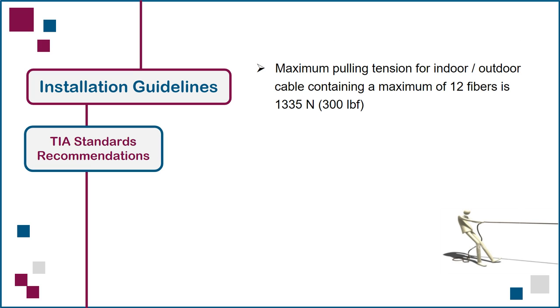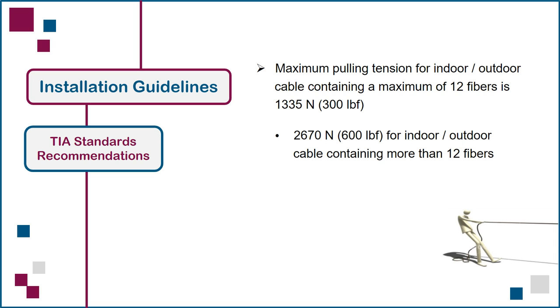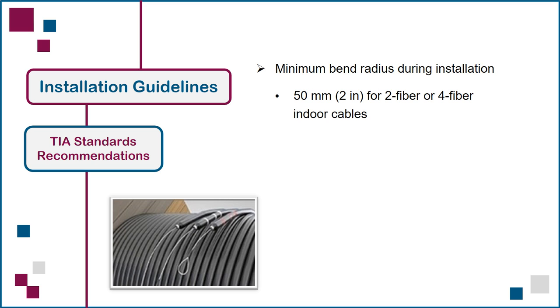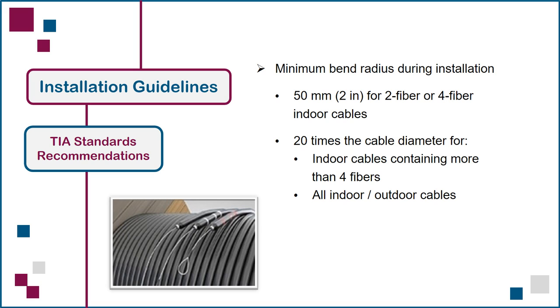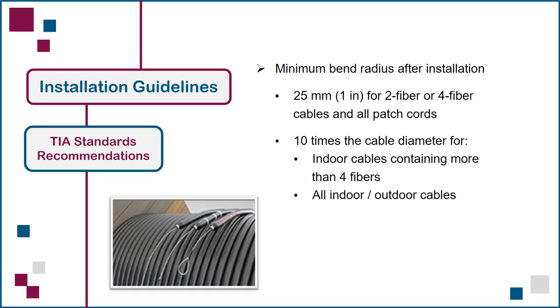For indoor-outdoor campus cables containing up to 12 fiber strands, the pulling tension must not exceed 1335 N or 300 lb force. This value is doubled for cables containing more than 12 fibers. The standards recommended limit for bending two fiber or four fiber cables during installation is no less than a 50 mm bend radius. For all other cable types, it's no less than 20 times the outside diameter of the cable. After the cable has been installed, these minimum bend radius values are reduced by half, and they also apply to all fiber patch cords. Note that these are all general recommendations published in cabling standards; any vendor can expand or reduce these limits for the cables or cords they manufacture.